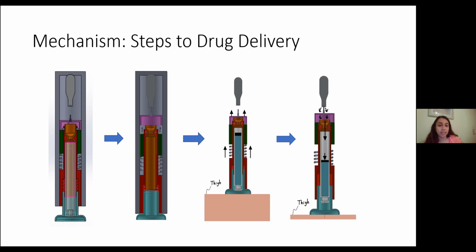What happens next is the balls that are here in this picture on the left actually fall into the red part, and the green little ejector that is connected to the spring pushes up and takes the entire mechanism and, with a lot of force, jets it into this cartridge that is connected to this hollow needle.